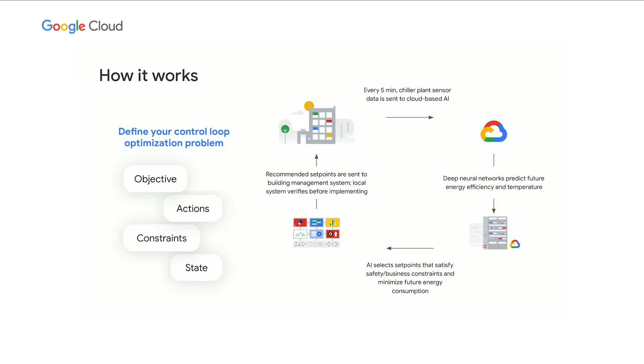Once you have that definition in place, you can go through this loop. Take an example where we're operating the chillers used to cool a data center. Every five minutes, we're collecting all the sensor data from the chiller plant and sending it up to the cloud-based AI. In the cloud, we're running the data through deep neural networks that can predict the future energy efficiency and the temperatures from all the various set point combinations possible. The AI will pick the right set point combination that will minimize your energy usage while obeying as many of your safety and business constraints as possible. Finally, it will make those set point recommendations available to your local building management system, which can validate and verify them before choosing to implement them locally.